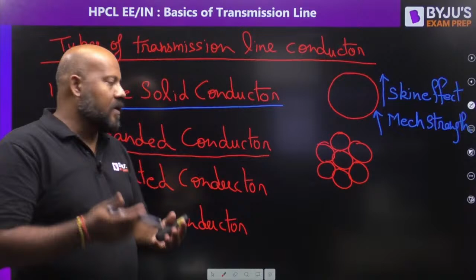Because even though you have reduced the skin effect by using a smaller cross section strand, still some skin effect is going to be present. And skin effect says that there is a tendency in the AC current to flow near the surface of the conductor. It means the core strands are not going to have significant current. So in order to increase the mechanical strength, what we are doing? We are removing the core strand that is made of copper or aluminum, and we are putting a steel strand. That is why it is called steel reinforced aluminum conductor.